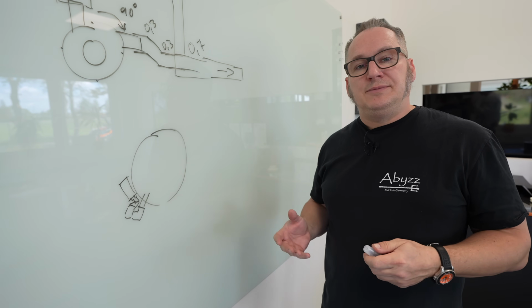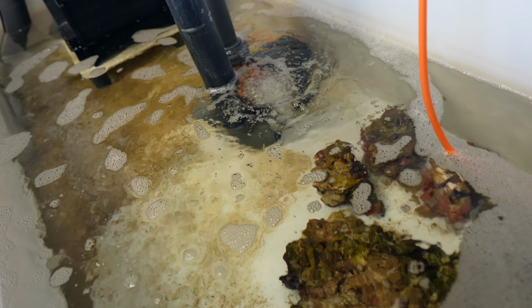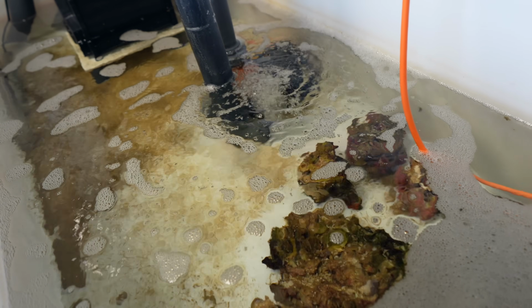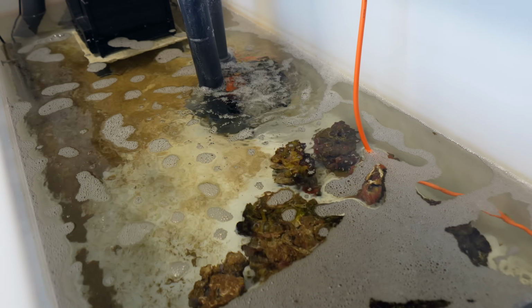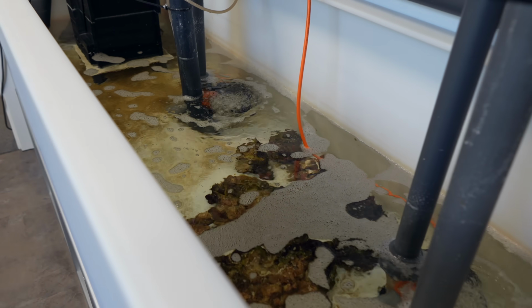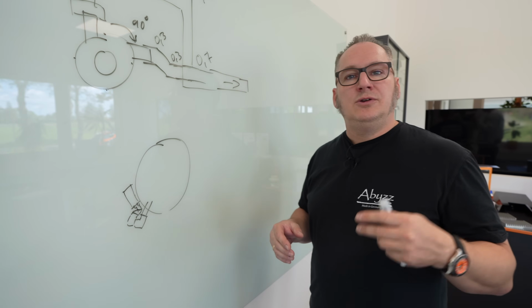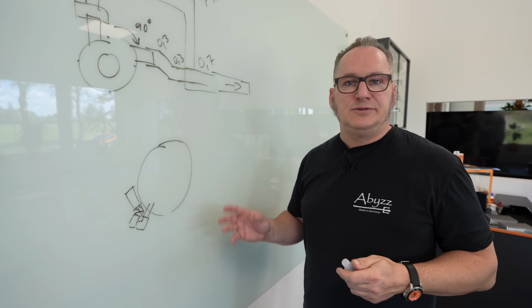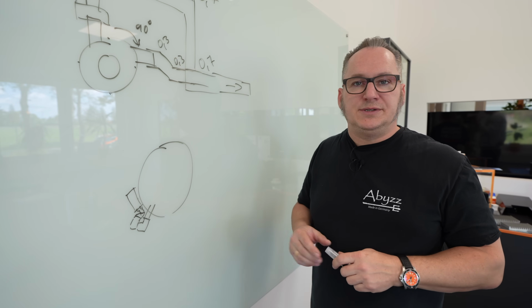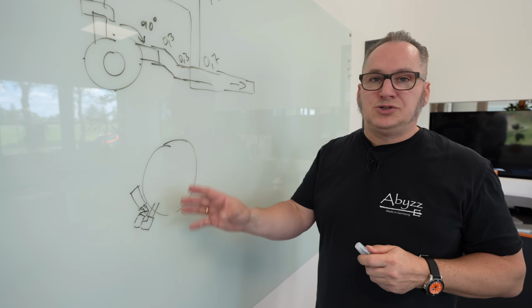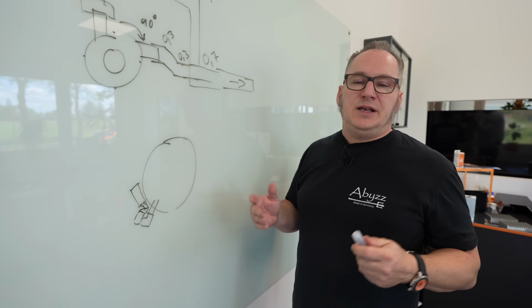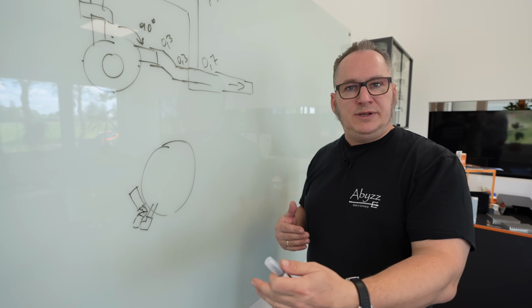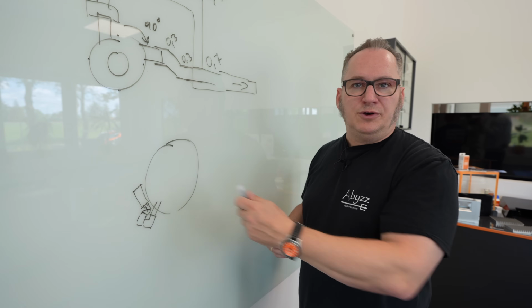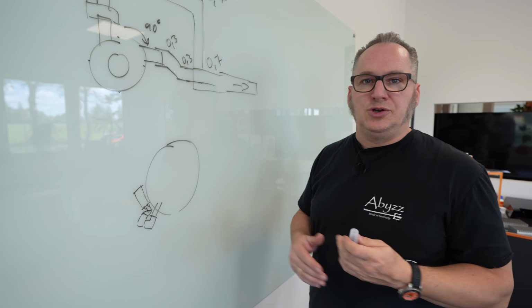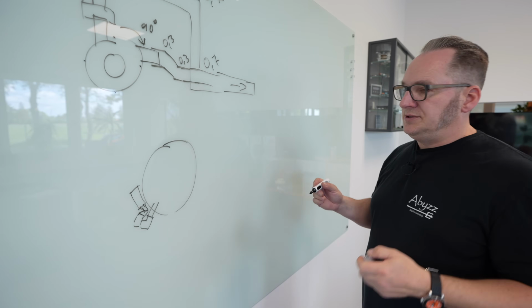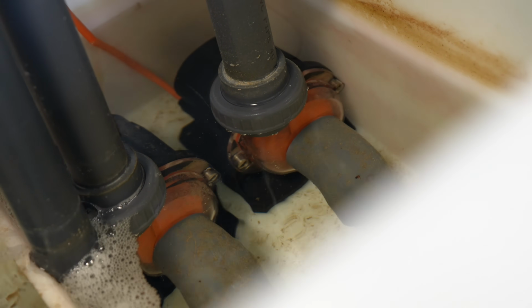We have designed the pumps to be most efficient when sucking in freely, so mounted below the water level. That's why these pumps are also very sensitive to any obstructions in the intake. If you block the intake like this, you're losing easily 25 to 30% of the pump's performance, and that's why it's very important to make sure that your intake is basically free. If you have a self-priming pump, they are more tolerant, but even for a self-priming pump, this would be great pressure loss.